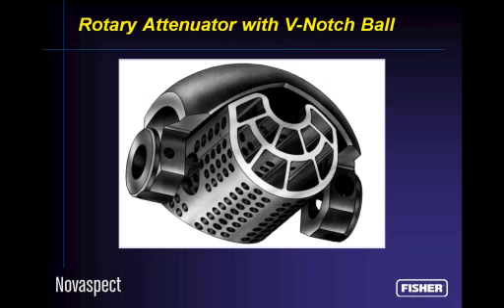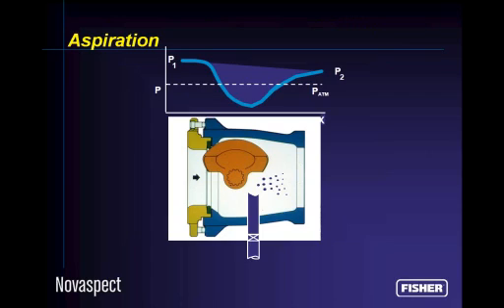We can even do this, believe it or not, in a plain old segmented rotary ball valve with an attenuator. We'll force the flow through various holes to achieve the same pressure drops in series and try to avoid cavitation. It's a little harder in a rotary valve, to be quite truthful. In some cases, we'll even take advantage of the fact that we've got some valves that have 60 pounds in the inlet, and they are headed back to a river. They're a cooling water valve. They're going to a lake, a cooling tower, whatever. There's a bunch of pipe getting it back to the river.